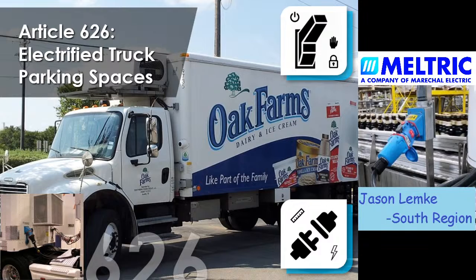So on motors, there's another additional thing that's very important in selecting a plug-in receptacle, which is to ensure that your plug-in receptacle has a horsepower rating, because there's an additional test to make sure that we can do 50 operations while that plug is seeing 6 times the FLA of the motor, which is the locked rotor condition. So our devices that have horsepower ratings may look overspecified from an amperage perspective, but you've got to remember that we're having to do that make and break as in a locked rotor condition. So that could be up to 6 times the rated FLA of the motor.